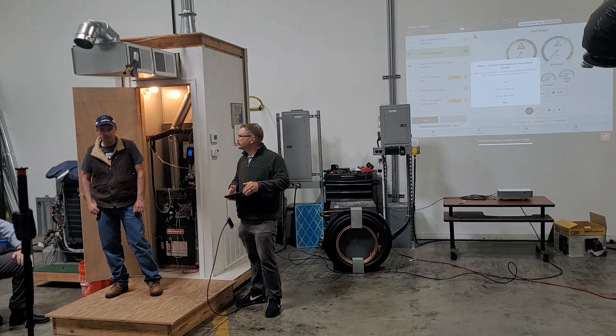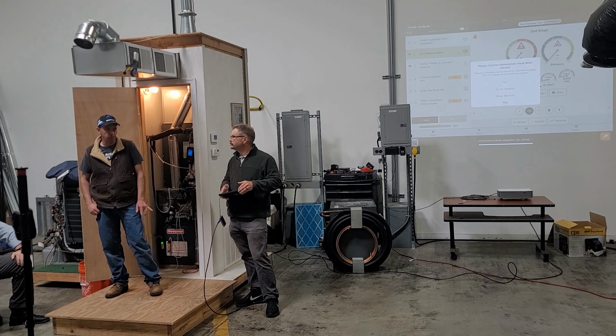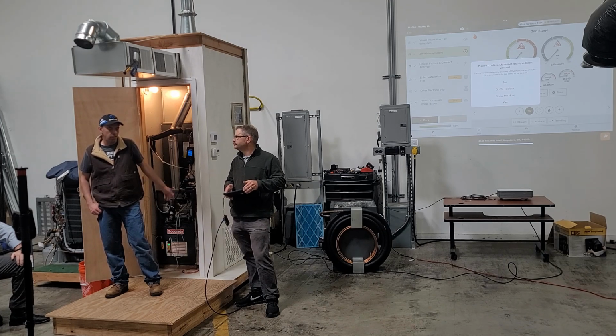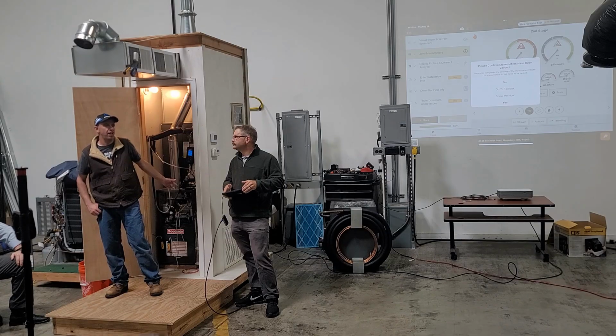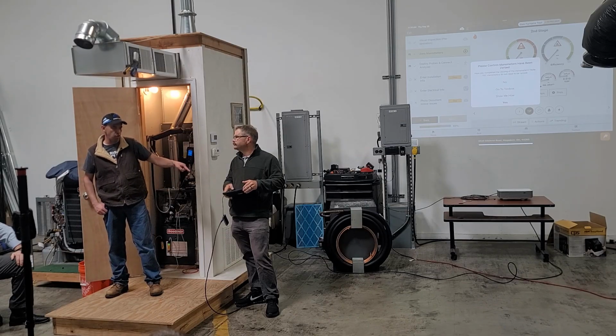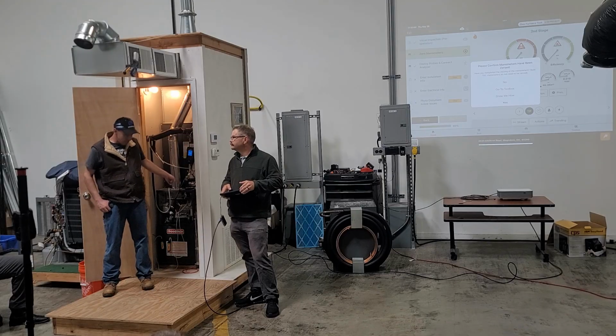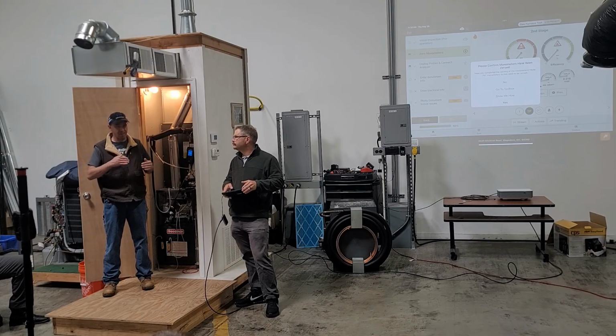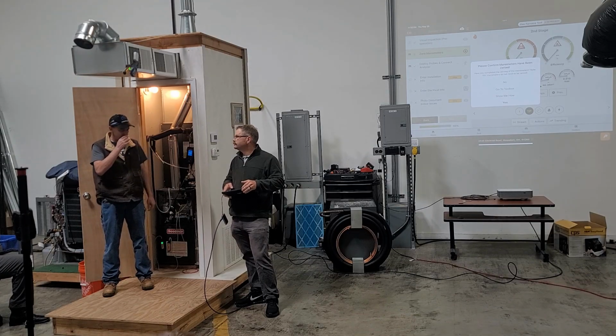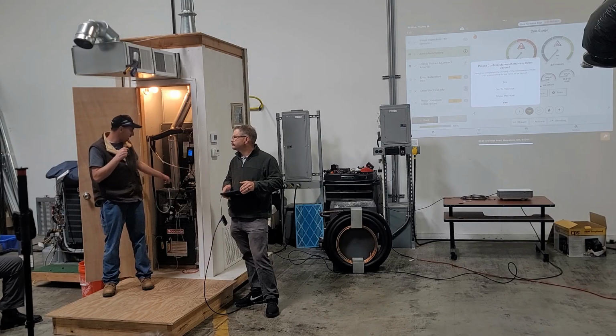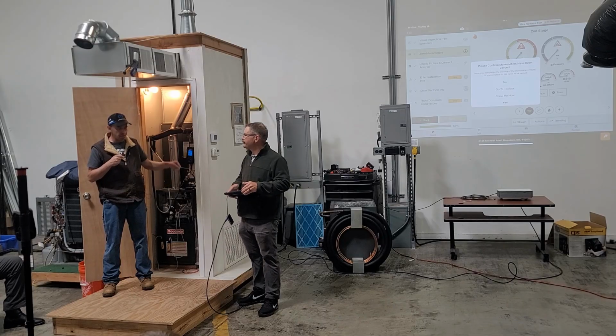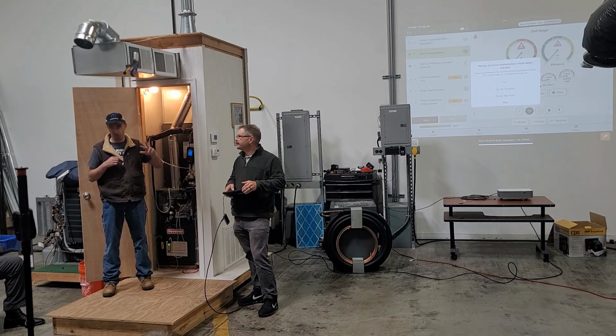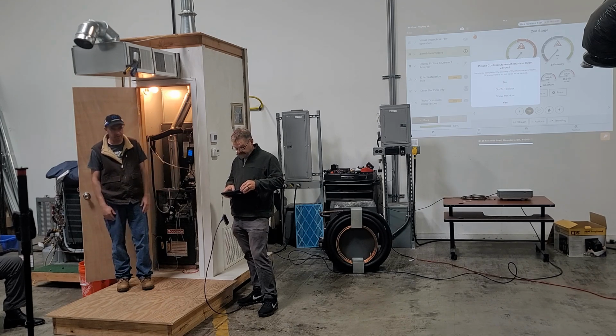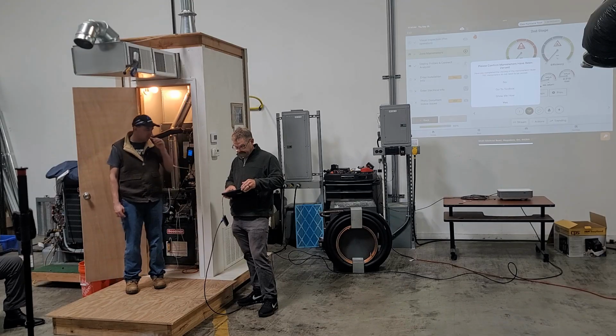Zeroing the manometer is a bit finicky, because when you zero it in MeasureQuick, if the manometer is at 10 inches of static pressure and you hit zero in MeasureQuick, the manometer will still say 10 inches. MeasureQuick is now establishing that 10 as zero, and any discrepancy in there is what it's calculating. So I prefer to zero it at the manometer, but then verify in Probe Manager that it's also at zero, so that both are zero. You want to zero the probe, then zero the app to that, if that makes sense - that's my OCD way of doing it.